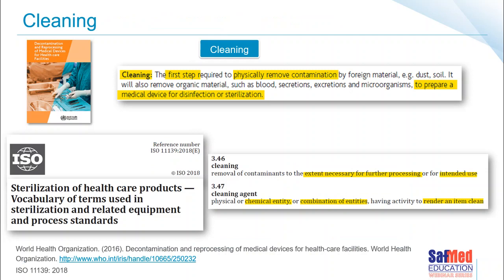When it comes to cleaning and definitions, one of the places one likes to go is straight to our guidelines that we can rely on and trust in, one of which is the World Health Organization guidelines. Cleaning, according to the WHO guidelines on decontamination, is the first step required to physically remove contamination from a device, including organic materials such as blood, secretions, excretions, and microorganisms, to prepare a medical device for disinfection or sterilization. If we go to the ISO standards — specifically ISO 11139, which covers the vocabulary and terms used in sterilization — it refers to cleaning as the removal of a contaminant to the extent necessary for further processing for the intended use of the device.